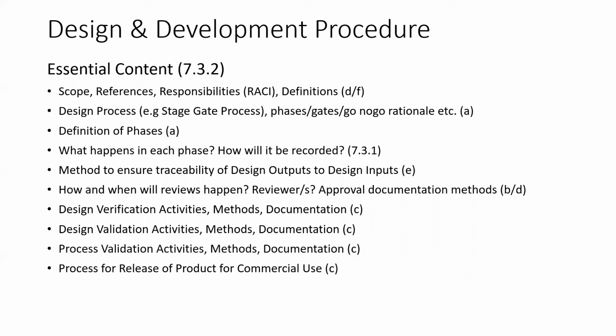How would we ensure traceability of design output to design input? Okay, so what is the method that we are going to follow to make sure that our outputs were in accordance with what the requirements of the device were as specified by users or as we specified in the beginning? So what is the process we followed? How did we document? And how can this be verified by an independent third party? The independent third party could be a regulator, the independent third party could be an auditing agency. So anybody who is going to come and audit is going to need to verify all these records and all this evidence. So the procedure needs to define how this work will be done.